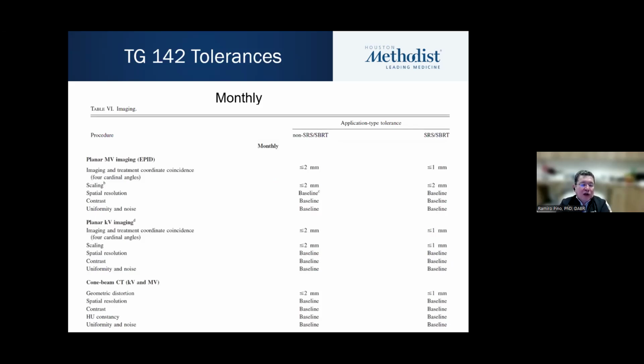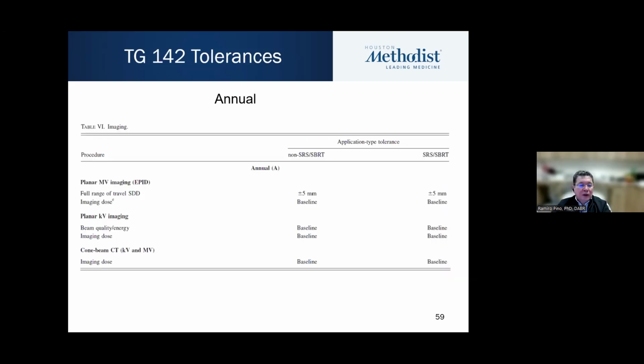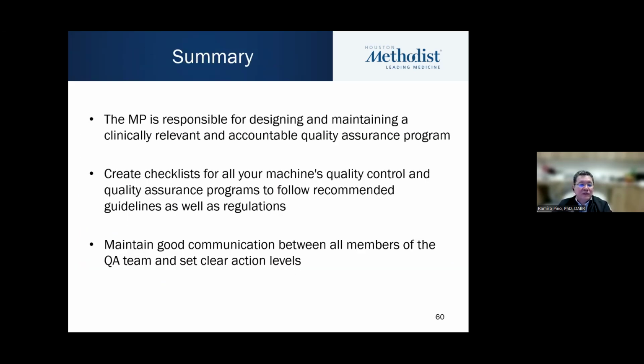Monthly, they're more detailed. We include also scaling, spatial resolution, contrast, uniformity, and noise. For annual, we go beyond the monthly. We check the full range of the motion of the EPID. We also measure beam quality and energy and imaging dose for kV and CBCT imaging. So this was shorter than I expected. I was talking really fast. In summary, the medical physicist is responsible for designing and maintaining a clinically relevant and accountable quality assurance program.